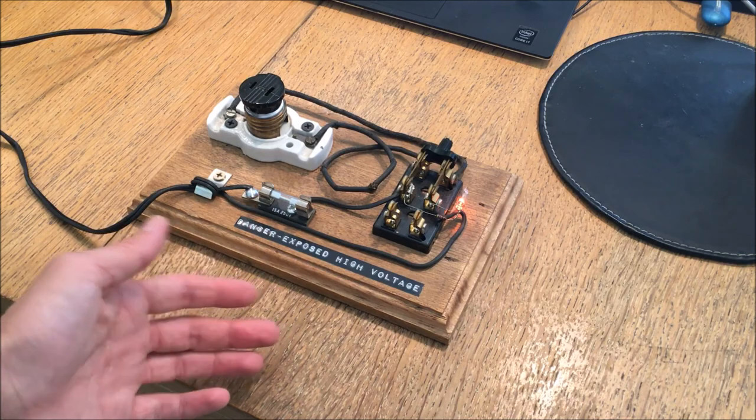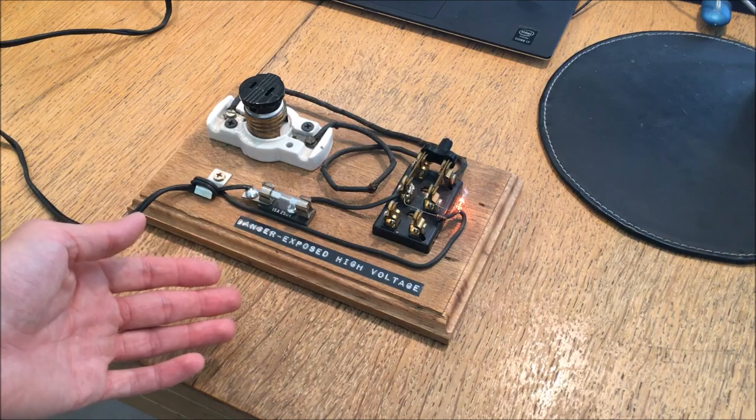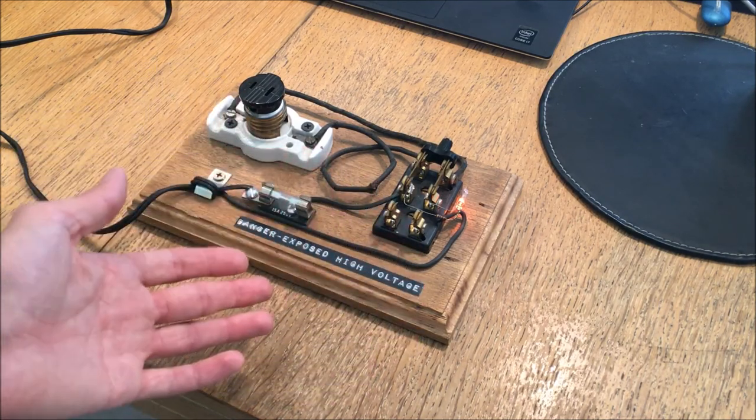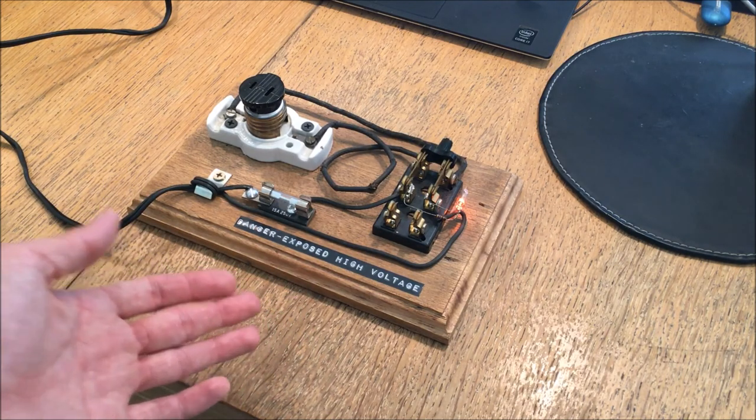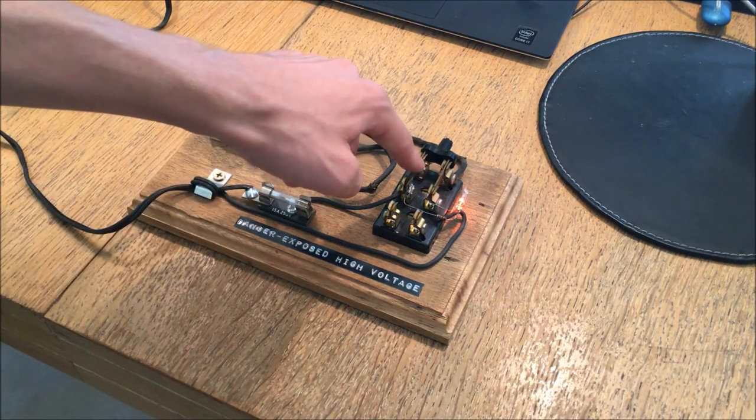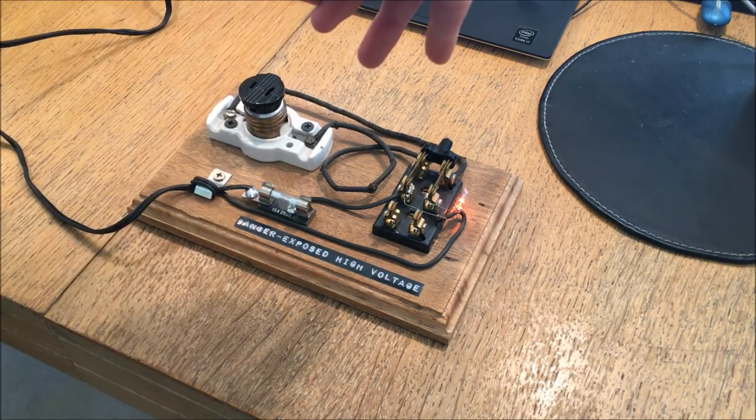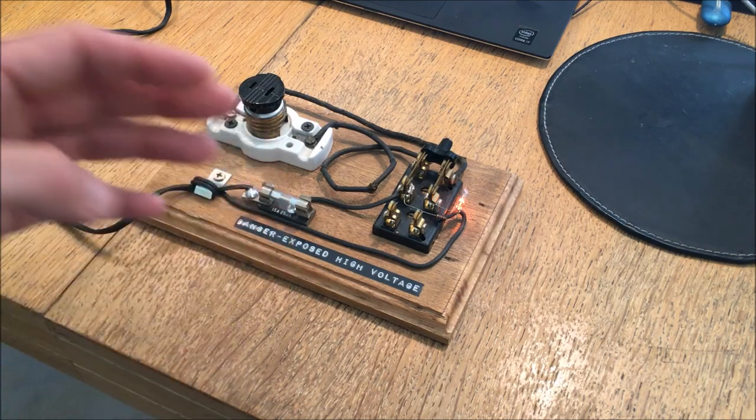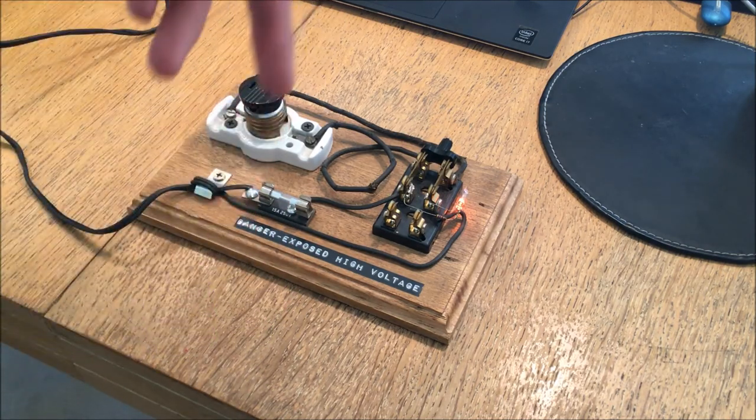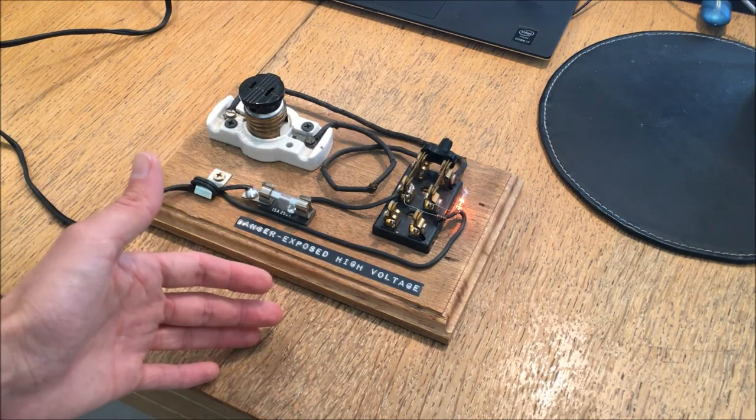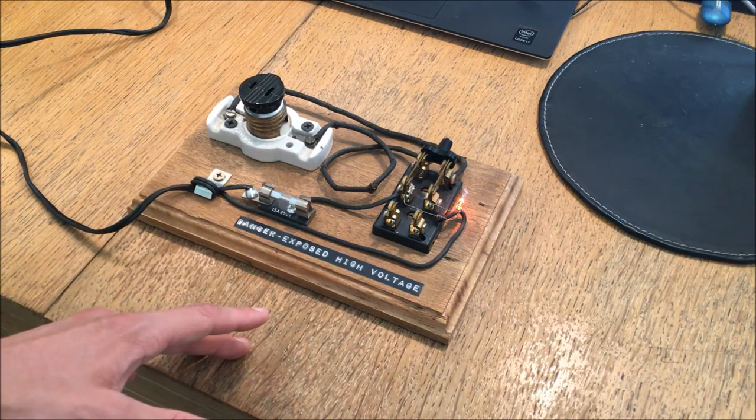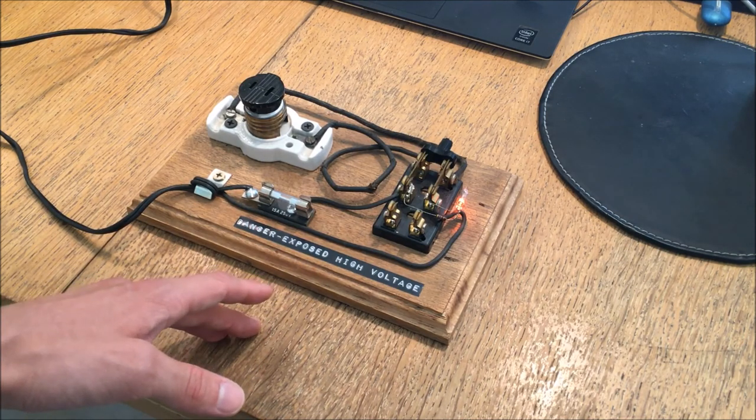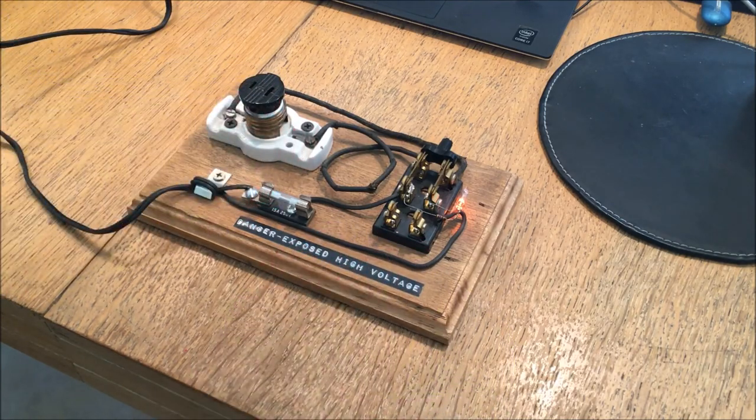I'll use this test board where you can attach different alligator clips at different points as an example of something that I might be working on which contains elevated voltage that could present an electric shock hazard when in use. As I mentioned before being at an isolated workbench I'm in no danger to touch either one of these at a given time. However if I were to touch both of those connections at the same time I would receive the same shock across my hand that I would if I had my hand on one side going to ground. Across one hand this is only an inconvenience, it could present a minor burn hazard or over long term could cause nerve damage but in and of itself is not likely to be fatal.